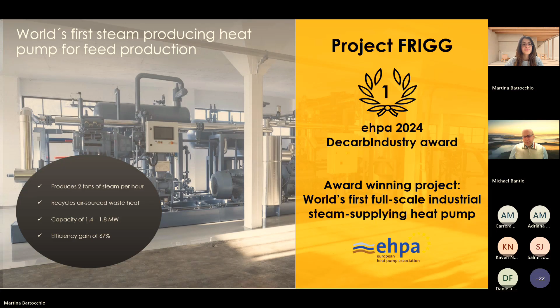Next slide, I have outlined maybe the points why our customer was going for such a solution in cooperation for this heat pump installation. Obviously, we improve the energy efficiency. The primary energy demand of the factory goes down 60 to 80% in that range with every megawatt or kilowatt hour of waste heat that we are recovering and bringing back to the factory. That's, of course, a very interesting value proposition. There is where you can save money.